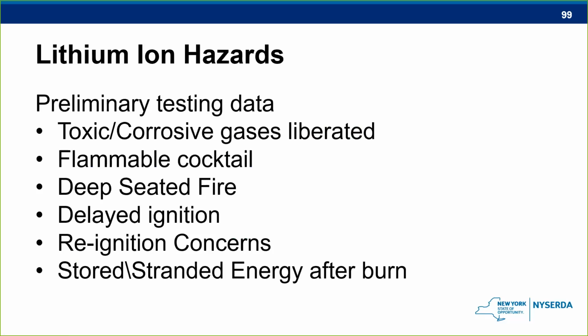But that's our biggest concern with this: if this thing does go south, we need to be concerned about the explosion hazard. And that's the reason for the deflagration venting in the enclosure that Jennifer had alluded to earlier in the conversation. So you can start to see the overlap now, why things are put in there for the code, because it's there to protect the firefighters if they were at a scene.